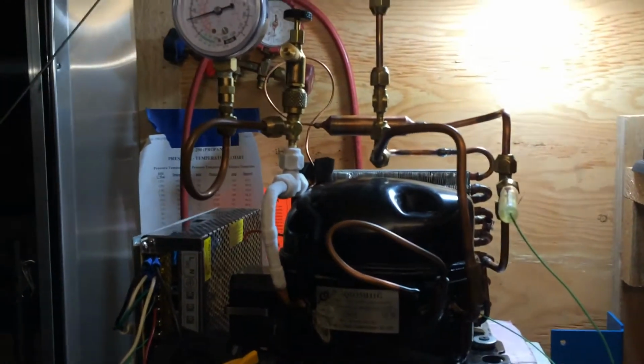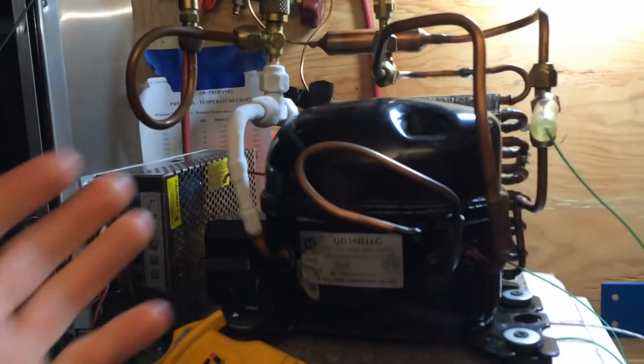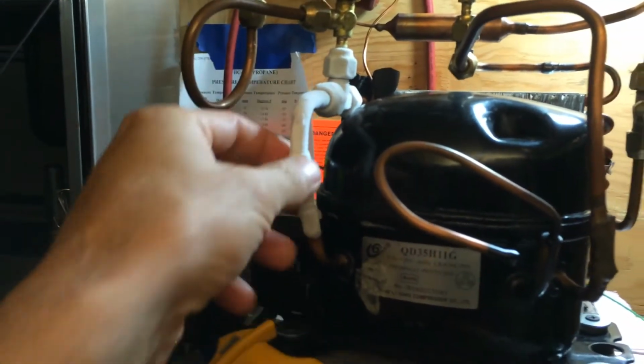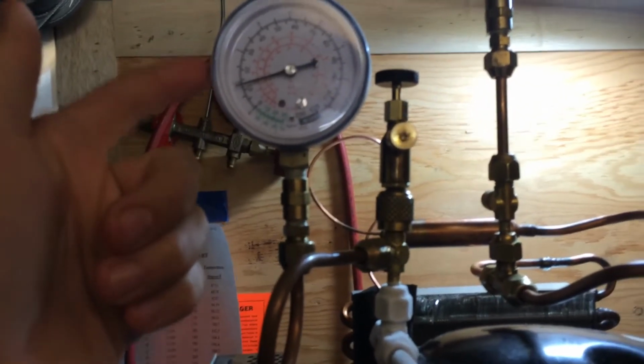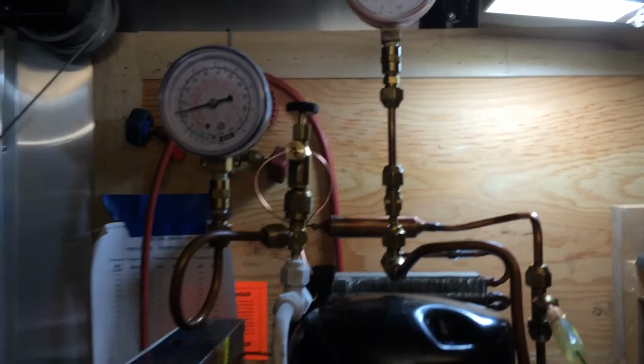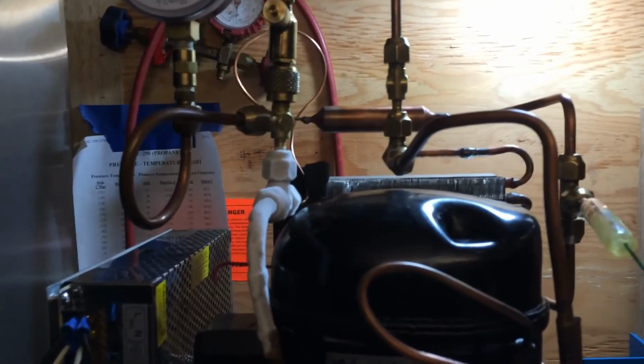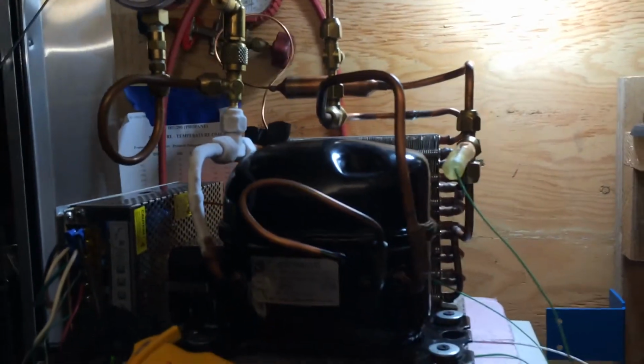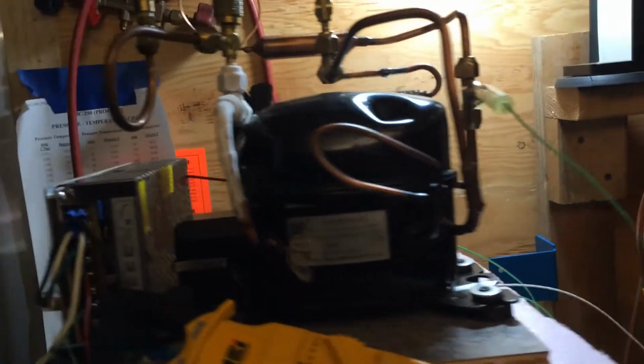that increasing the size of the evaporator and the surface area of the evaporator will allow me to store a little more refrigerant in the low side. You can see we're getting some freeze back here, and maintain higher suction pressure, keep my compression ratio a little bit smaller, increase volumetric efficiency, higher mass flow through the system, move a little more heat more effectively and more efficiently.